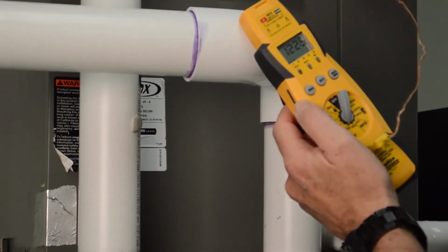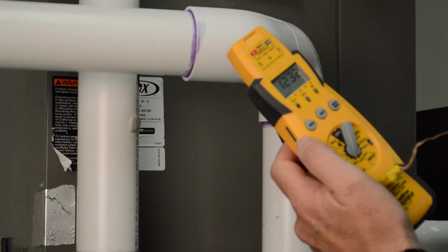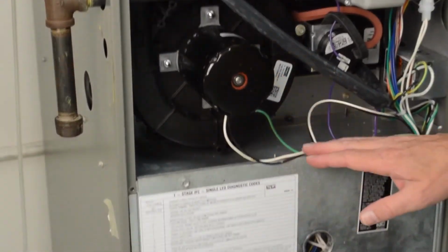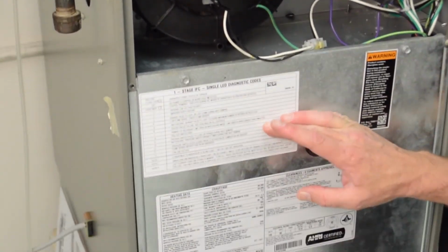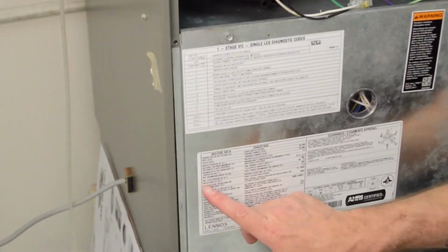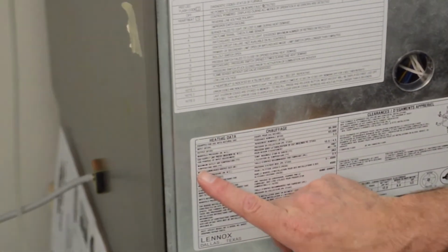Okay, it's leveled off at about 122.5 degrees, so we're going to subtract the 66.5 from the 122.5, and that's going to give us our temperature difference. 66.5 from 122.5 is 56.0 degrees. What we're going to do is, with that number, we're going to go down to the furnace nameplate itself, check to see what our temperature rise across this furnace is supposed to be.